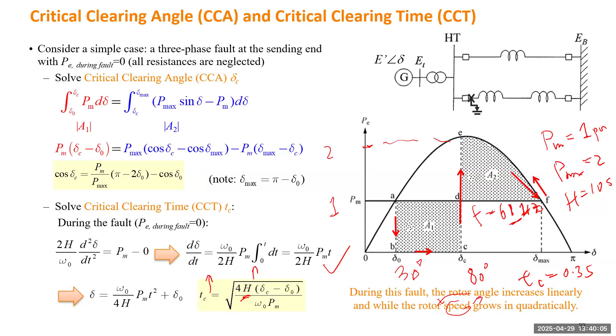So lastly, the generator internal voltage magnitude E prime. This one can be controlled by field excitation. If you can design a controller based on the exciter, the exciter will detect the fault. If the fault happens, that will increase the field current and also increase the E prime. That will make the PE increase during the fault or post-fault. So that gives you a bigger decelerating area, and that will improve the stability.